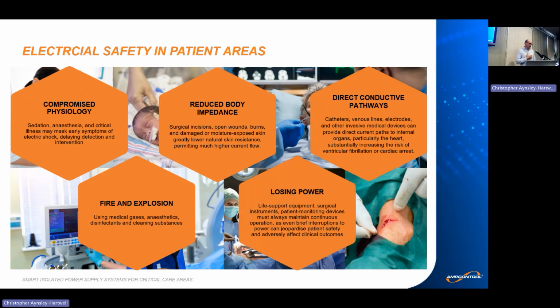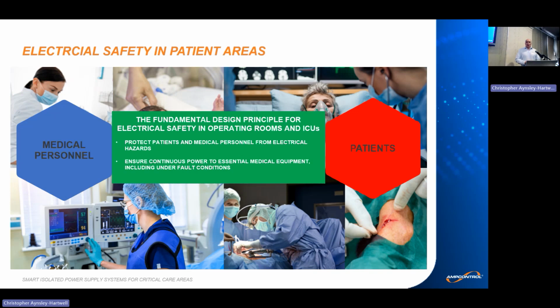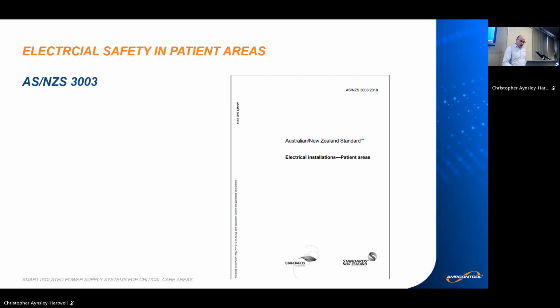But on the other hand, intensive care units and operating rooms are heavily dependent on a wide range of medical equipment. Systems like life support systems, surgical instruments, and patient monitoring systems must remain operational, because any power interruption can jeopardize patient safety and affect clinical outcomes. And for all these reasons, we need a solution that can provide the highest level of protection to patients and medical personnel against electrical hazards, and at the same time maintain power availability to critical medical systems even under fault condition.